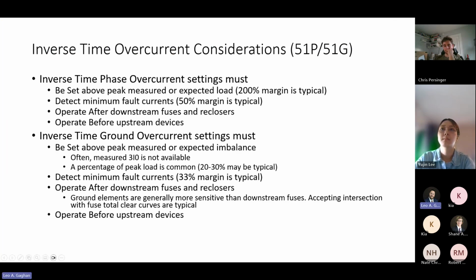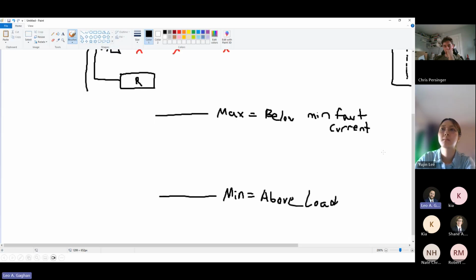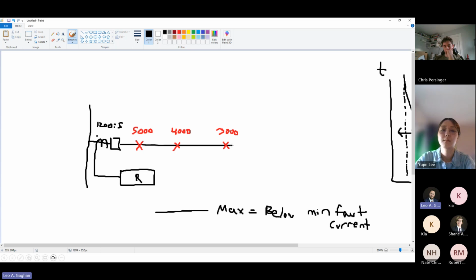So after those two goals, our next two goals are related to coordination. As we talked about, if we've got that recloser, and a fault happens right here, we need to make sure that the recloser is faster so that it can clear it, and that the relay upstream is slower so that it can stay in service, because there's likely going to be other customers that we want to continue to provide power to.